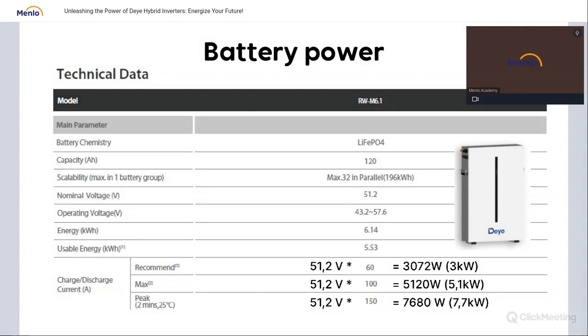5.1 kilowatts. We can peak up to 2 minutes, stress the battery up to 150 amps, but still we have 7.7 kilowatts maximum discharge from the batteries. We have up to a 12 kilowatt three-phase inverter, and the maximum power of the battery is 7 kilowatts, but we shouldn't process more than 5 kilowatts. You see the difference in the numbers. If you want to exceed that number, you need to use 2 batteries.